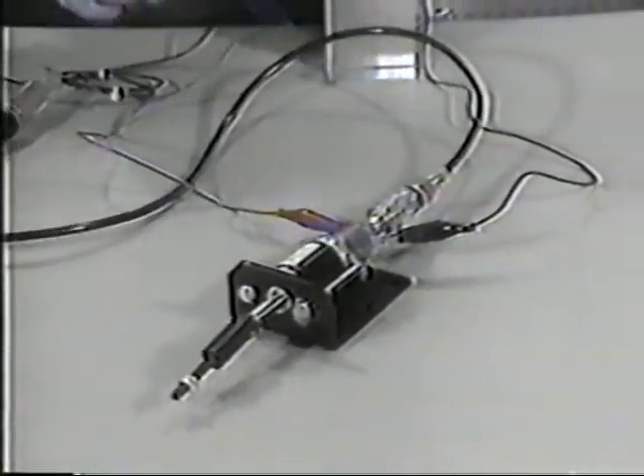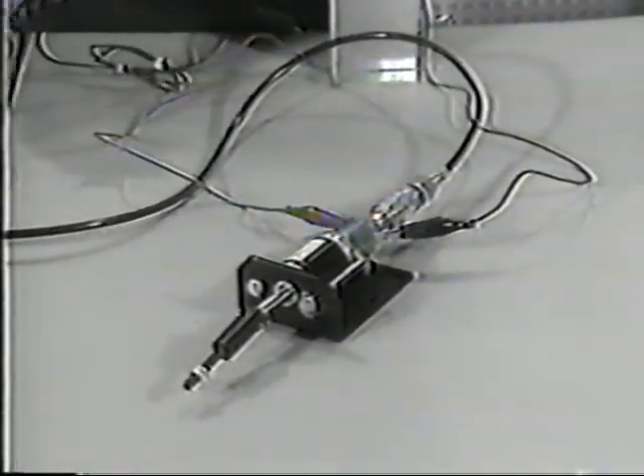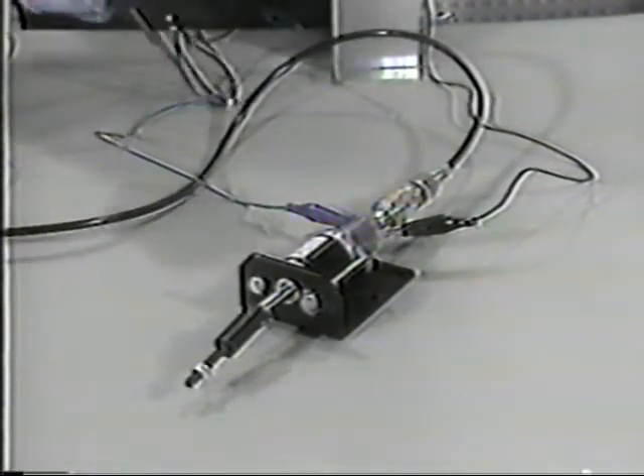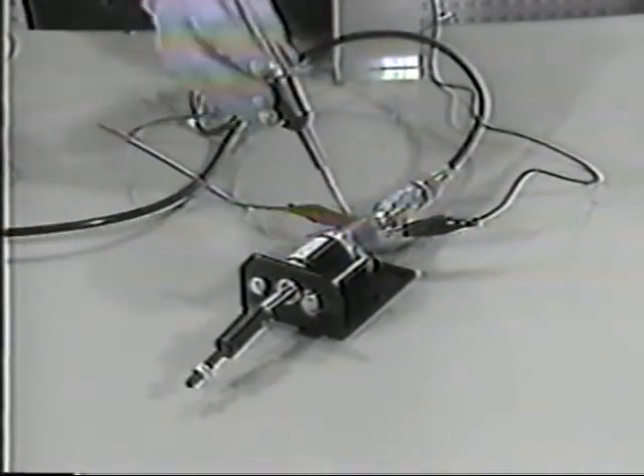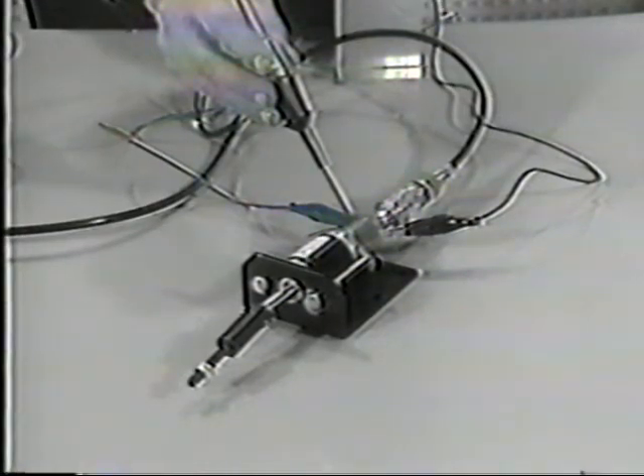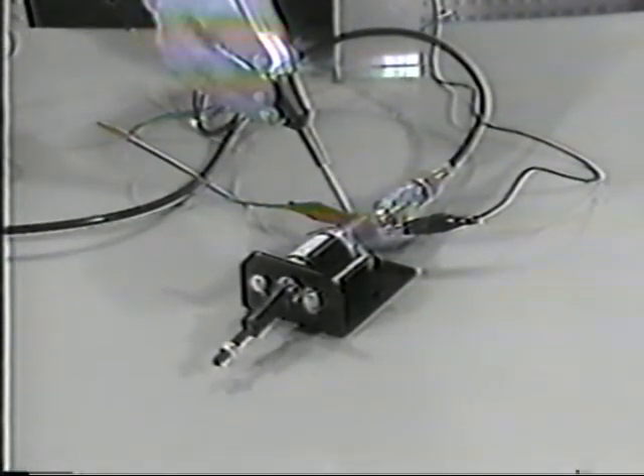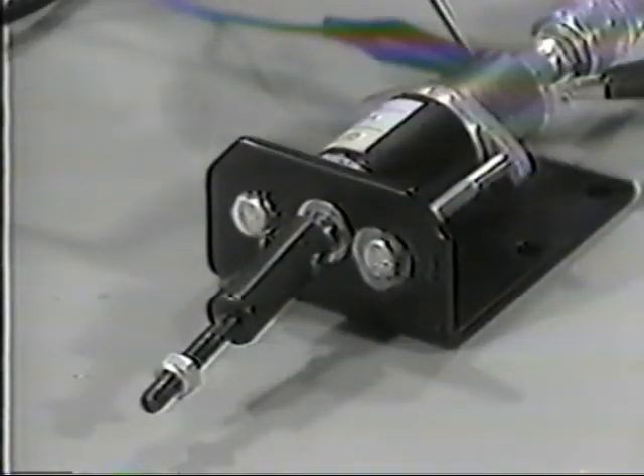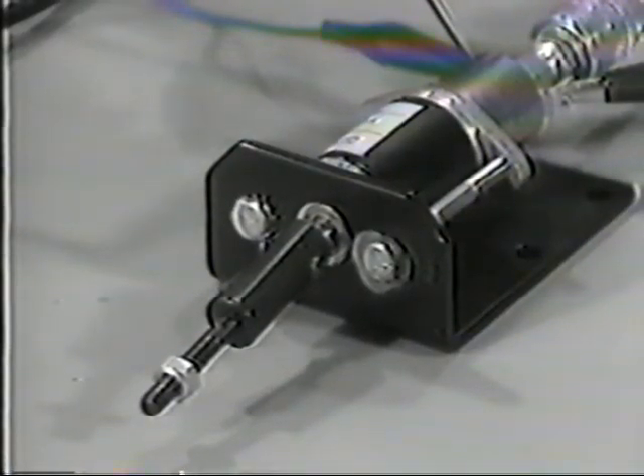That wraps up alarm-only engine protection systems. Let's now take a look at alarm and shutdown systems. All KYSOR shutdown systems begin with a key switch which is connected to a fuel shutoff. The fuel shutoff may be either an electric solenoid or a KYSOR air-operated actuator. With the KYSOR actuator, when the key switch is turned on, voltage reaches the solenoid valve, causing it to close, exhausting air from the cylinder and allowing the piston to retract. The linkage turns on the fuel and the engine can be run.